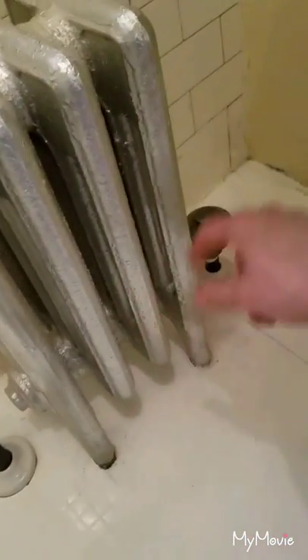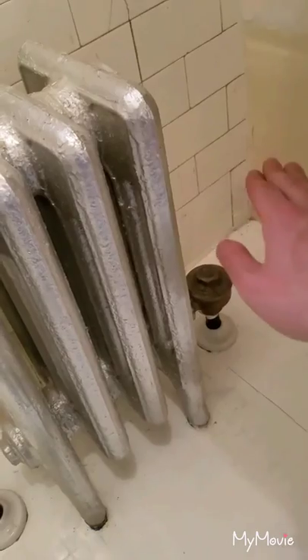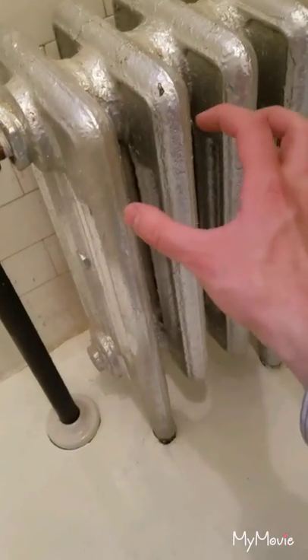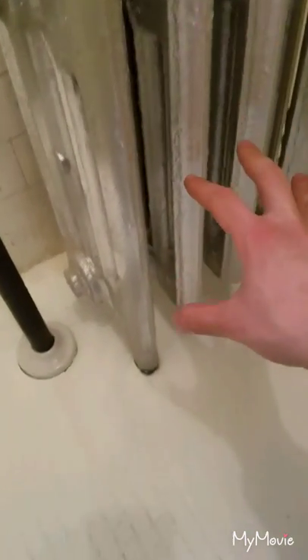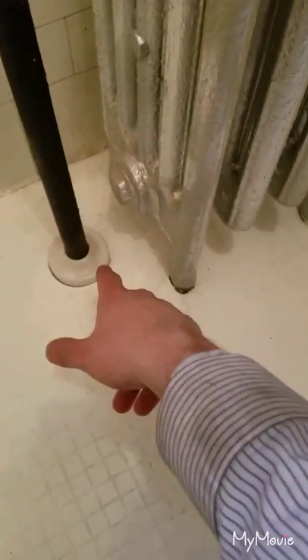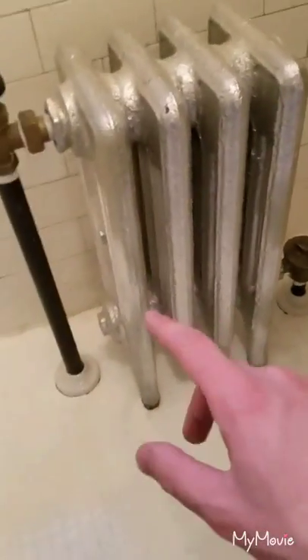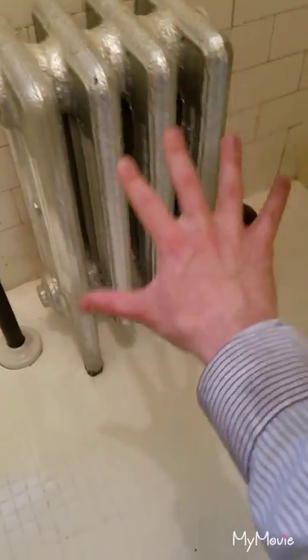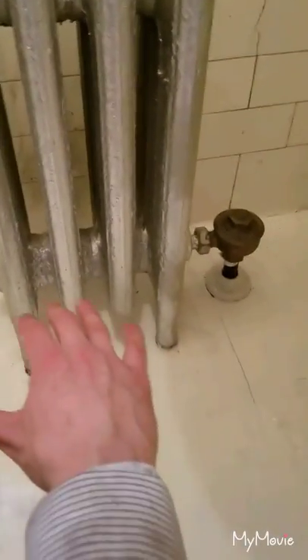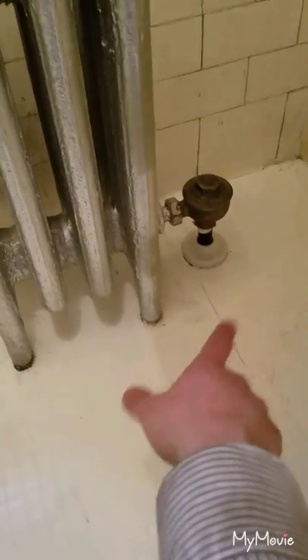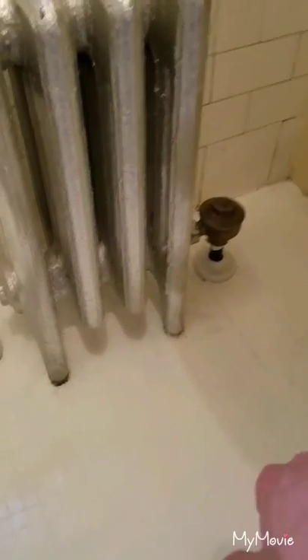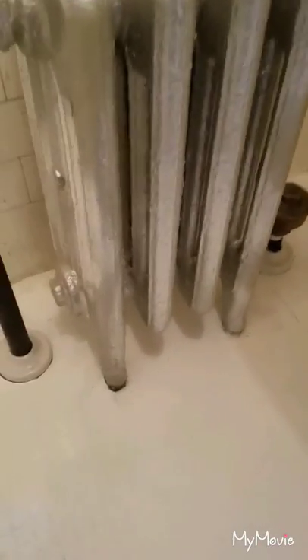Steam would fill the radiator, let out the air. When steam hits the air vent, it'll close. The radiator will just give off that heat, and then that steam turns back to condensate and goes back down. The same pipe, but this is a two-pipe steam heating system, so steam comes in the top, works its way down, and goes out down the trap, down the return riser, and back into the vacuum tank.